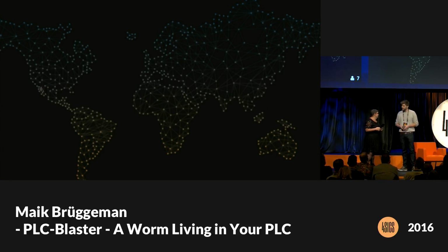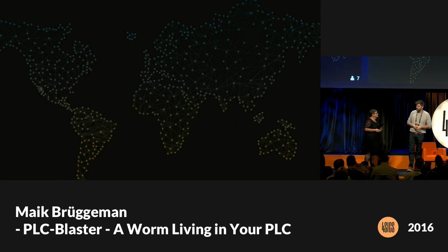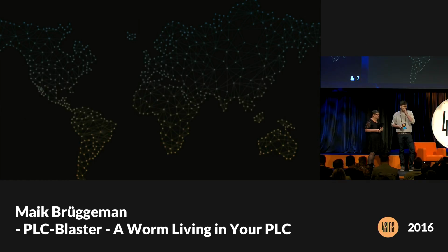I think it is possible to detect this because what is happening here is that one PLC transfers a program to another PLC, and this is strange behavior. Usually you expect the engineering station to do such operations. But the problem here is that you need to understand the protocol, because the protocol is used for changing the outputs, and that is a usual feature which the PLCs do to each other. So you have to look deep into the protocols and understand what this message is exactly doing, and then you can recognize things like this. But okay, so it's possible, but it will take some time.